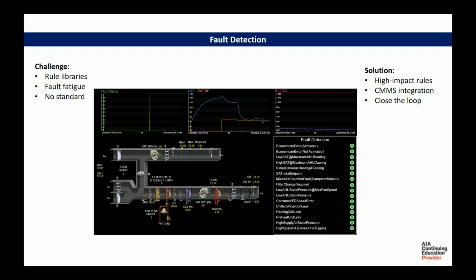If we go through that analytic and think about it, the temperature probes in an air handler, when they're installed, are probably accurate to plus or minus a degree, maybe even 2 degrees. And they drift over time too. So the perfect out-of-the-box one goes in at plus or minus a degree and a half, we'll say. What that means is that with that plus or minus 2 degrees, there's a likelihood, not a strong chance, a likelihood that you're creating faults that reflect the accuracy of a sensor and not the true operation of your system.